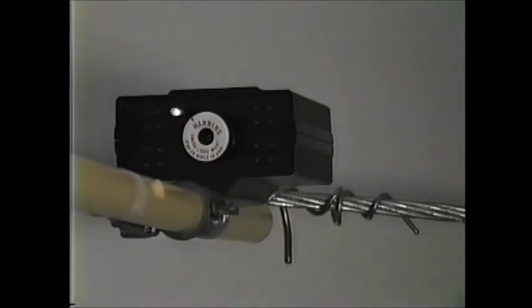There are some situations which will cause an extra bank of lights to come on or to slightly desensitize the HLS 5. Anything that affects the electric field around it will have this effect, such as installing it close to the ground or close to another energized phase.